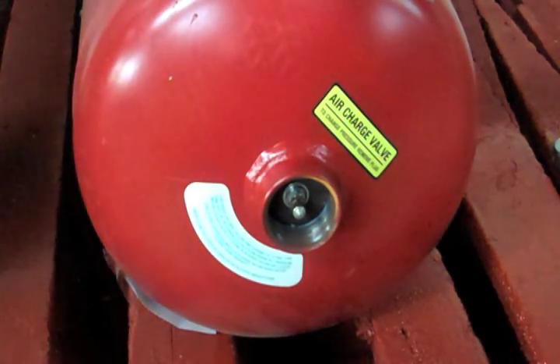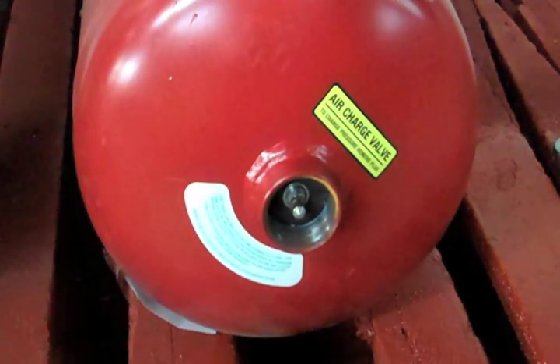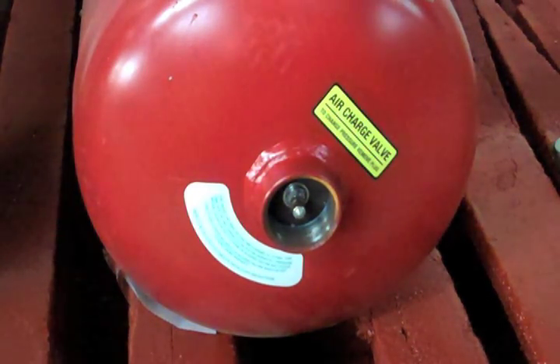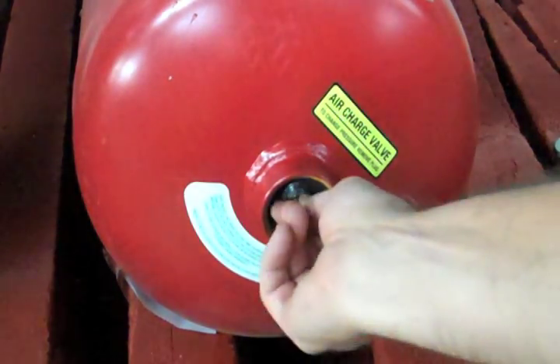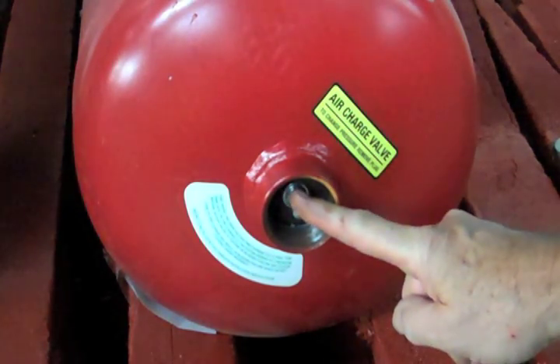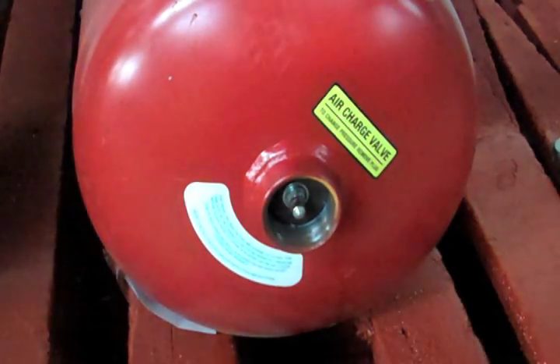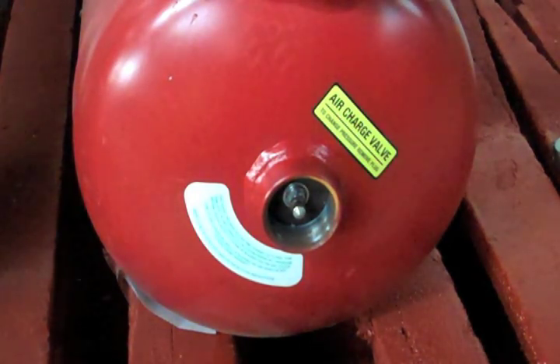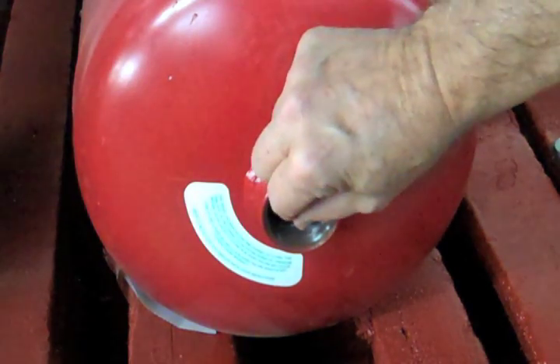Why before you connect it? Pay close attention to this. Why do you pre-charge it before you connect it? If you hook it to the 70 pound system and it's 12 pounds in there, when you check your pressure right here, it's going to show you 70 pounds because that air is now compressed by the pressure coming in from the other side. So before you connect it, before you connect it, you need to pre-charge this.